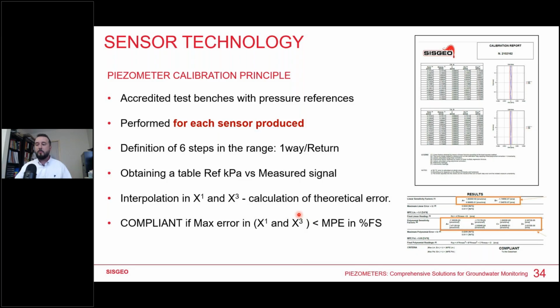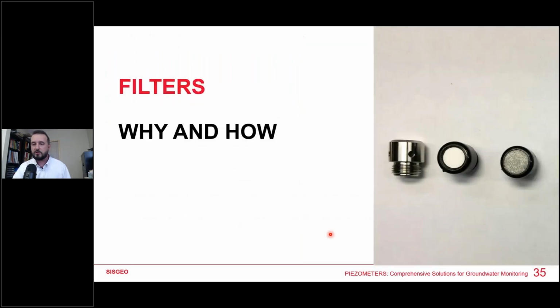So the sensor is compliant. Here you can see on the bottom right part, compliant. It's compliant if the error taken from this interpolation is lower than the maximal permitted error that is stated in our datasheet. That means that when you are reading a datasheet from us, the value is the worst that we can give to the client. So the sensor is always better than that. If the sensor is not compliant, it goes to the trash. So you are certain that it's always a good sensor.